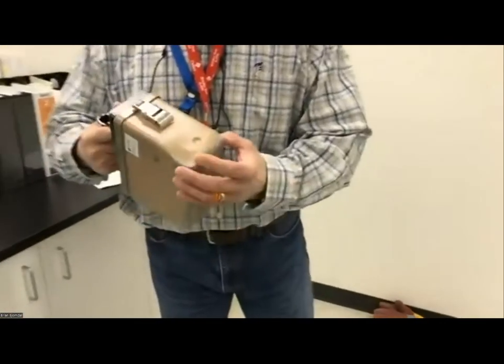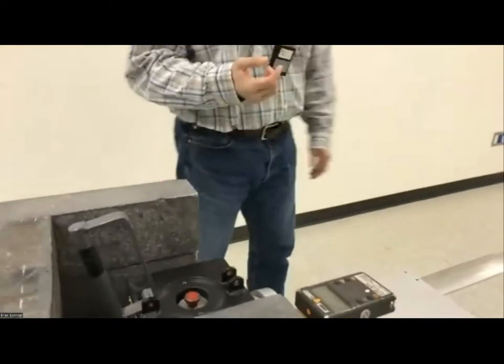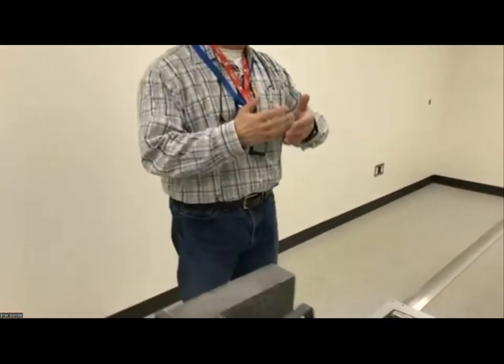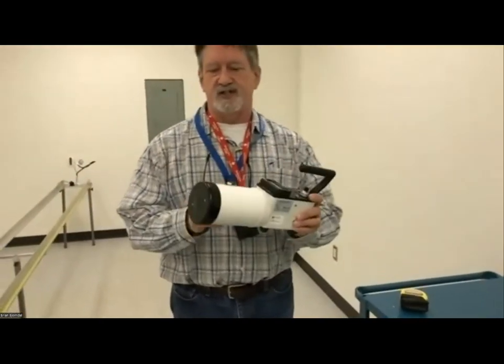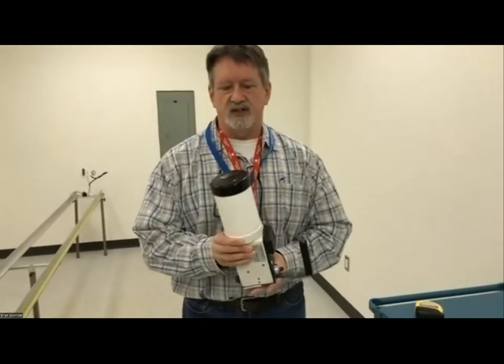Right. And really measurements, yeah. Also, for some survey meters which may have a certain point of measurement marked, can you set up to that position or depth? You see on this one here, it actually tells you where the detector is. Some instruments will not say that, but some instruments will have marks on them where the detector is. I don't think this one does. It has the ribs here. That may be where the detector is. But depending on the instrument, we'll check the manual to determine where that detector is if we don't know. But the idea, you're right, is to make sure that, because the detectors have width and dimensions to them, we're getting the detector in the right location. So whether it's the center of the detector or at the face of the detector, we can determine from the operations manual. Particularly in some detectors like these here, are you measuring to the face of the ion chamber or to the center of the ion chamber? So we make sure that's all determined during the calibration to make sure that we're getting it right.